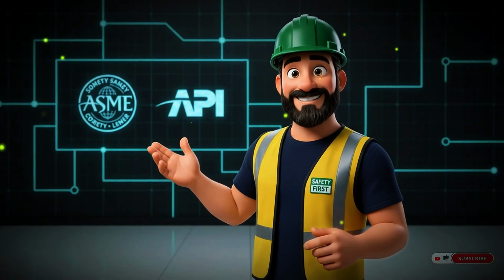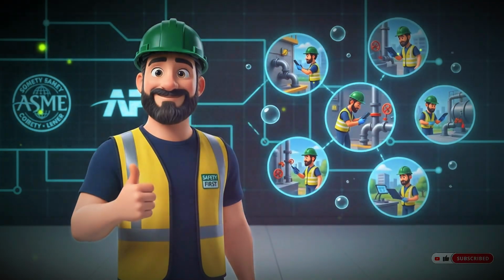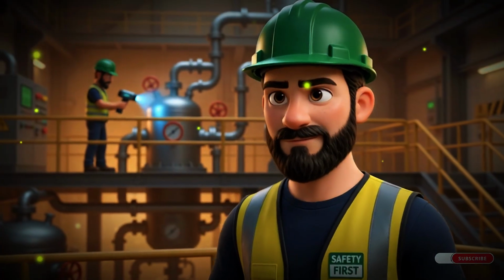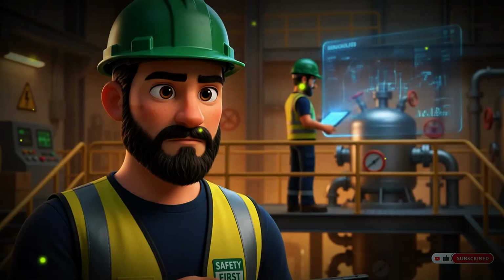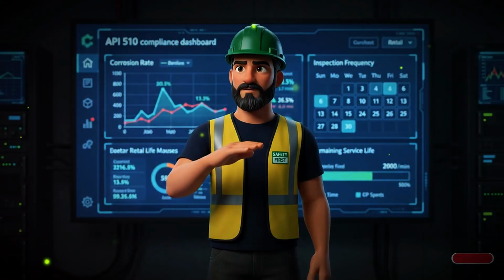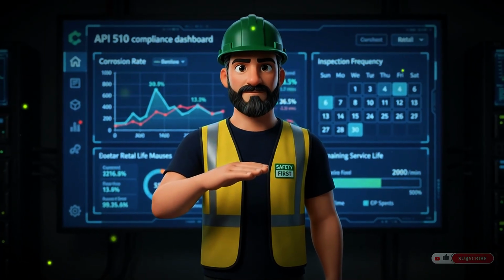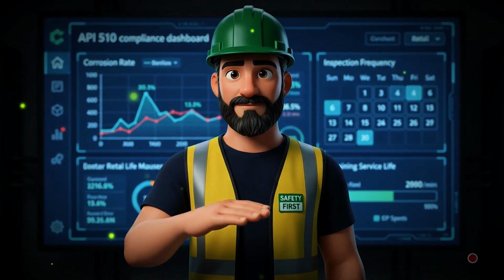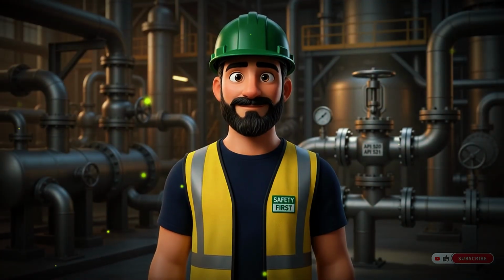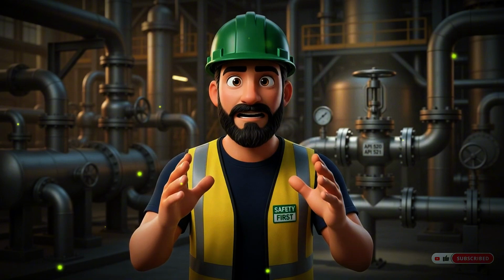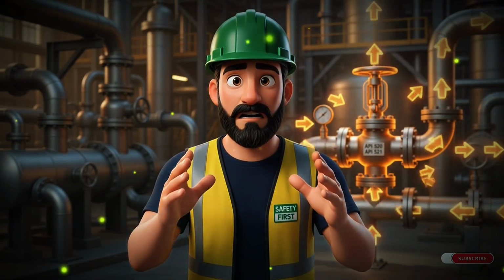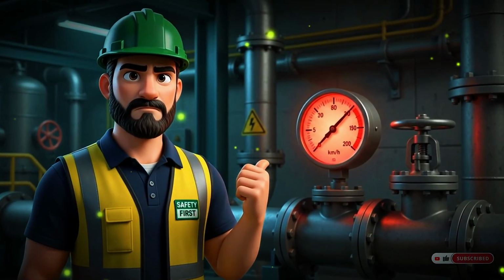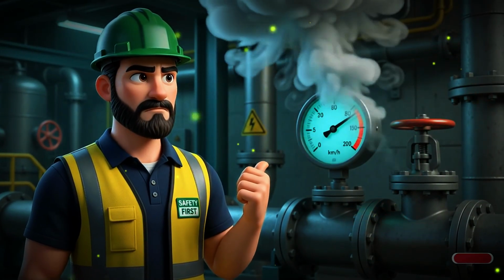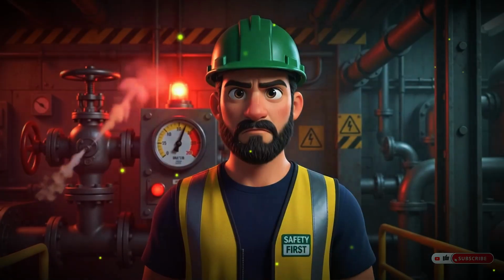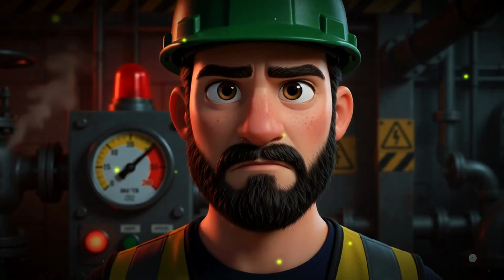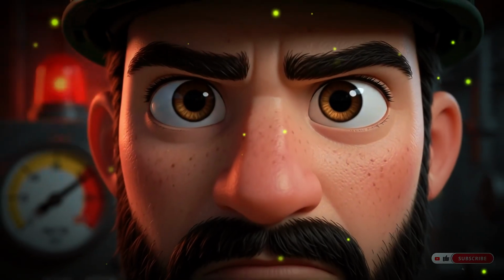The American Petroleum Institute, the API, stepped in to complement design standards with standards for operation and inspection. API 510, for example, defines how to inspect pressure vessels already in service. It establishes the acceptable corrosion rate, the frequency of inspections, and the criteria to determine whether a vessel still has enough remaining service life to continue operating safely. API 520 and API 521 address something critical: pressure relief systems. Those valves you see on refineries that open automatically when the internal pressure exceeds the safe limit. They are the last lines of defense before disaster. And when they fail, or when they are ignored, the result can be catastrophic.